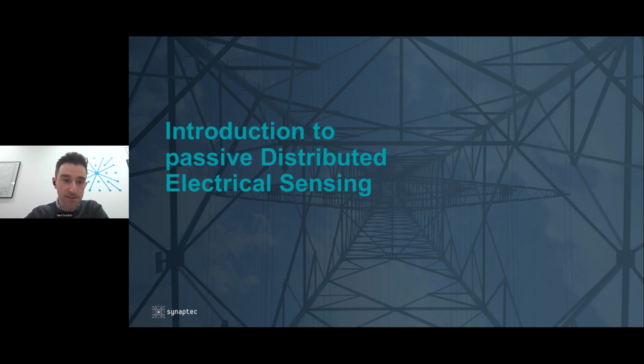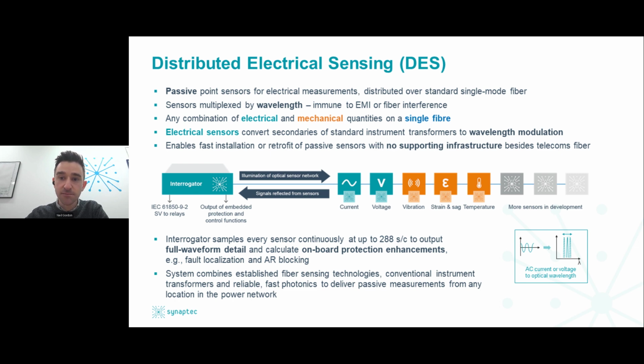And we refer to this technology as distributed electrical sensing. So this technology allows us to deploy passive point sensors for electrical and mechanical quantities distributed in series over standard single-mode optical fiber like ADSS. This means that we can deploy any combination of electrical and mechanical sensors. So that means sensors for current and voltage, as well as strain, temperature, vibration, and overhead line sag, using existing single-mode fibers, standard telecoms fiber. Each system consists of a central powered interrogator system and a string of sensors which are wavelength multiplexed over single-mode fiber. Now, all of those sensors operate in reflection.